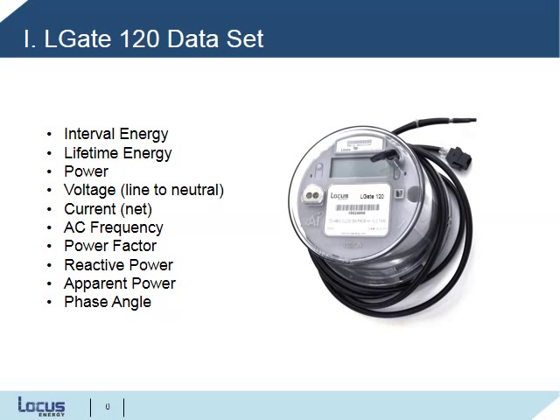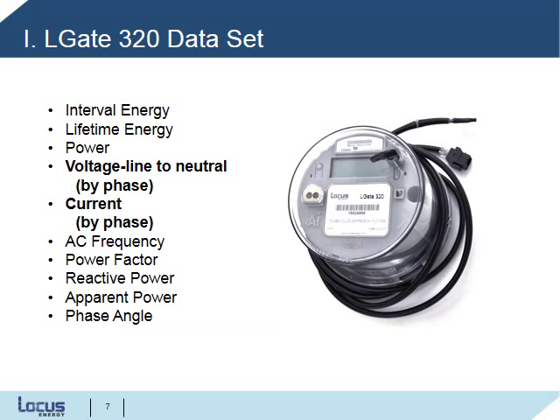Now, the LGate 120 dataset includes interval and lifetime energy, power, line to neutral voltage, and net current. In addition, the LGate 120 will measure AC frequency, power factor, reactive and apparent power, and phase angle. This expanded dataset provides much greater insight into site commissioning and post-installation O&M. In addition to these variables, the LGate 320 measures line to neutral voltage by phase and current by phase.